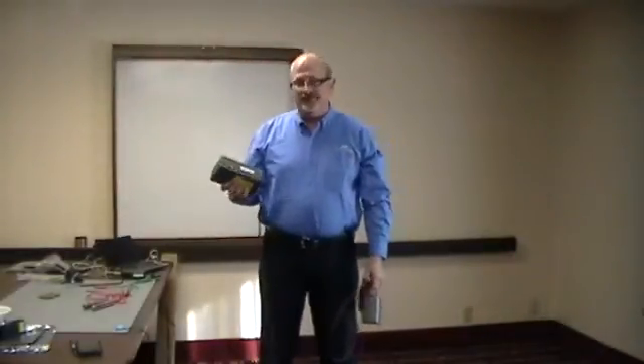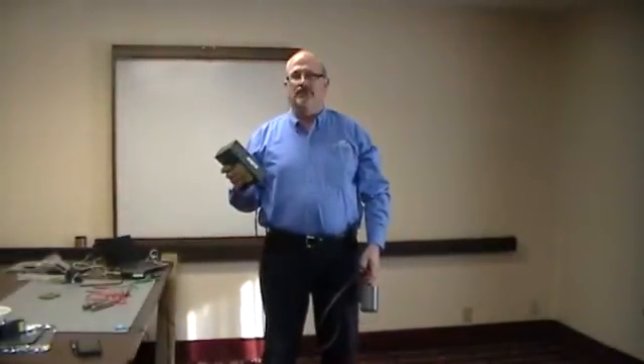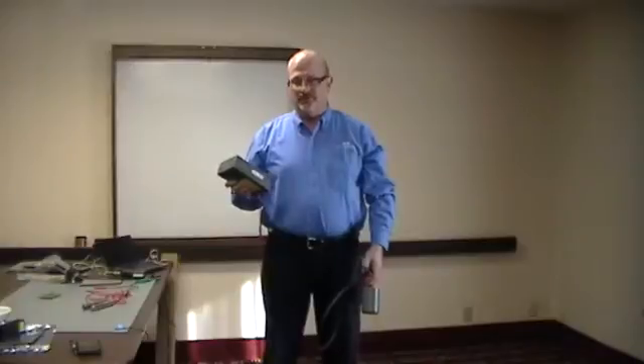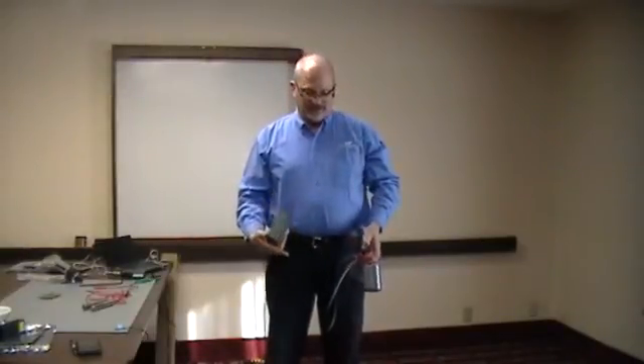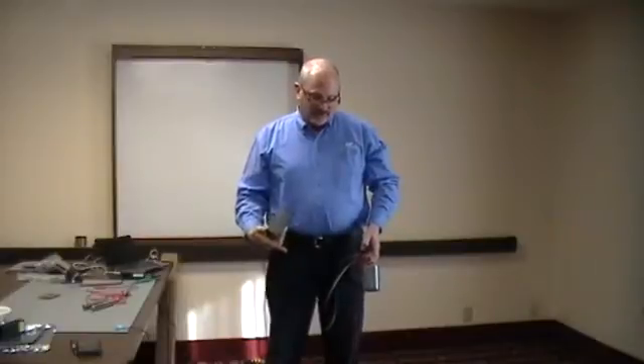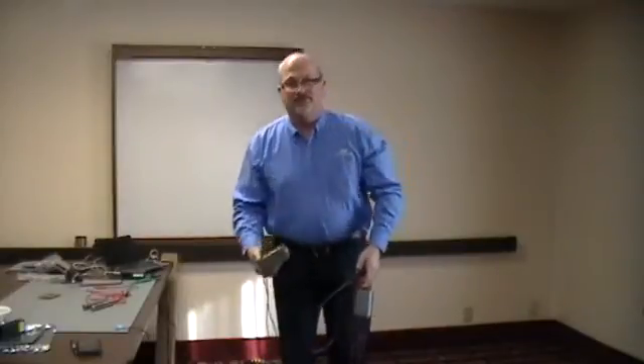We're going to use a megohmmeter which has a test voltage of either 10 volts or 100 volts, two five-pound weights, and we'll set them three feet apart on the test specimen and test the voltage across those two points and record the values.